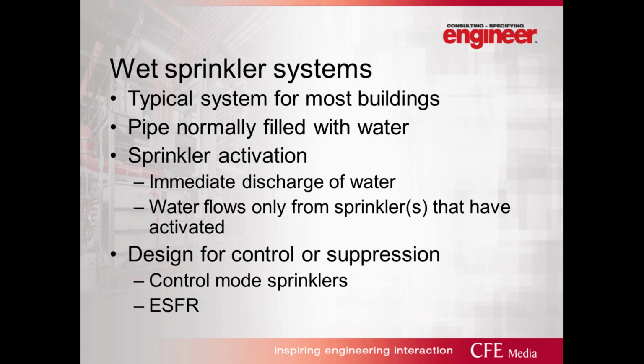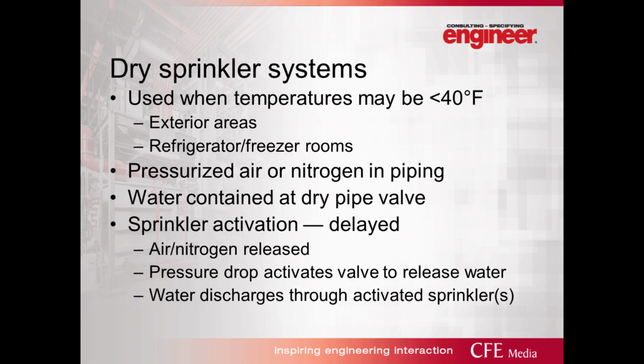Wet sprinkler systems can be designed for control or suppression. Control mode sprinklers are typical types of sprinklers used in protection of storage occupancies. Many of you may know ESFR, early suppression fast response. These are specific sprinklers designed to actually extinguish or suppress a very high damaging fire quickly and actually suppress it instead of just controlling it. So you can design for one or the other, and the application really depends on what type of hazard you are dealing with and what you're trying to achieve with the sprinkler system.